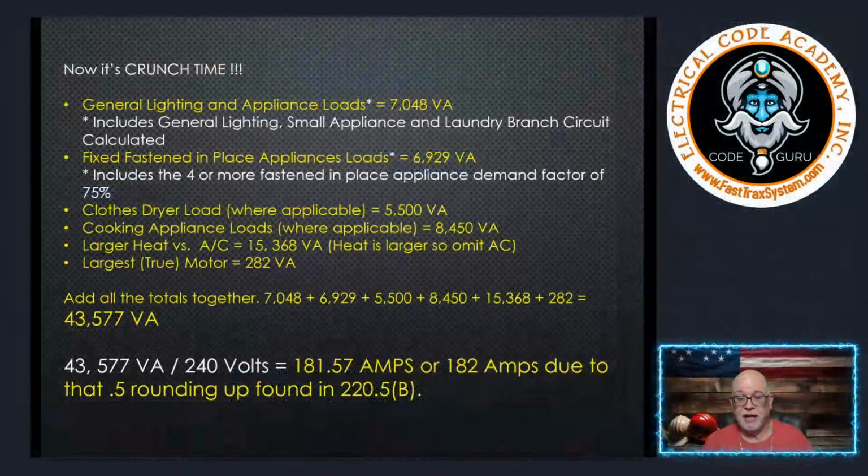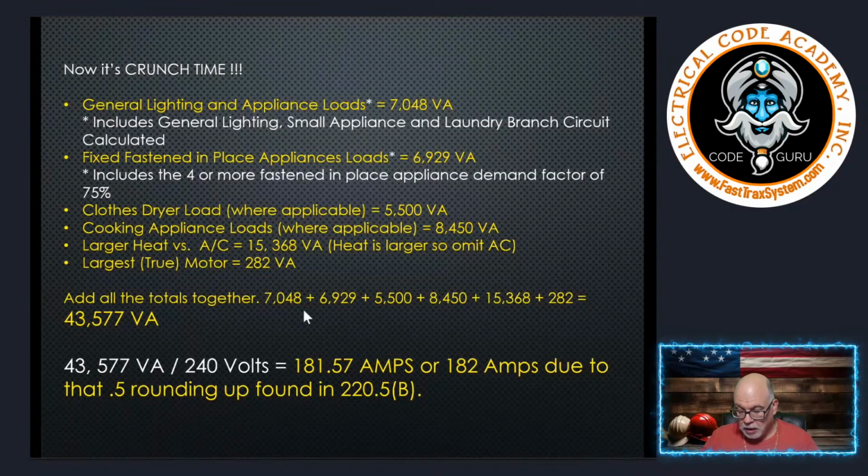Okay, here we've got to focus. You could go running over to 310.16, folks, and simply go to the 75-degree column because of the terminal and temperature limitations of 110.14(C), and say, okay, I'm just going to find a conductor that can handle 182 amps and be done with it. But there's something you've got to remember. This is not an exception.